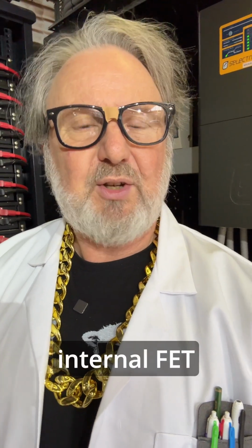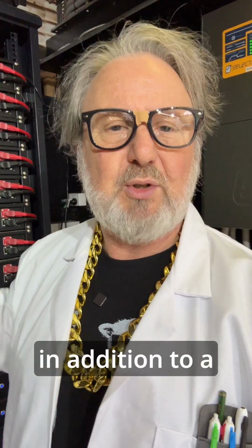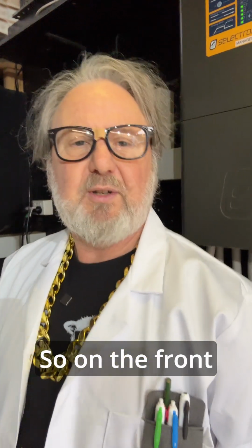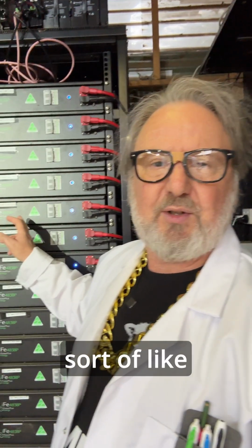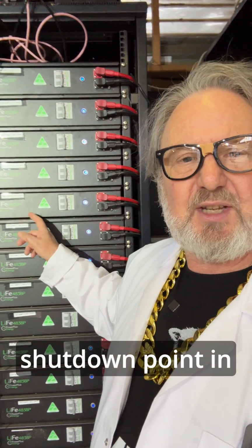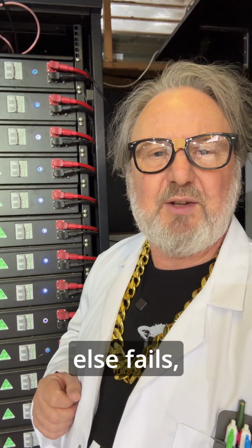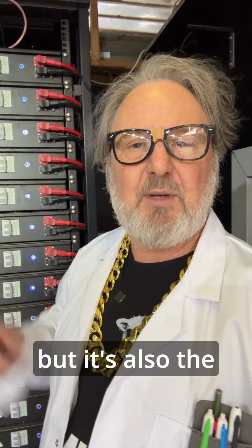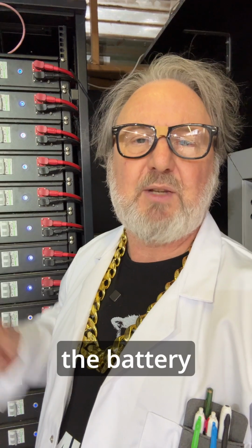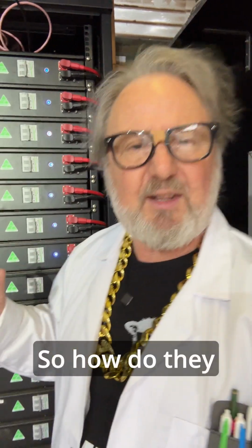They've got internal FET switches in addition to a circuit breaker. So on the front here, we've got some circuit breakers, and these circuit breakers are sort of like the ultimate shutdown point in case anything else fails. The circuit breaker can still trip in an overcurrent situation, but it's also the on-off switch for the battery modules. So how do they protect themselves?